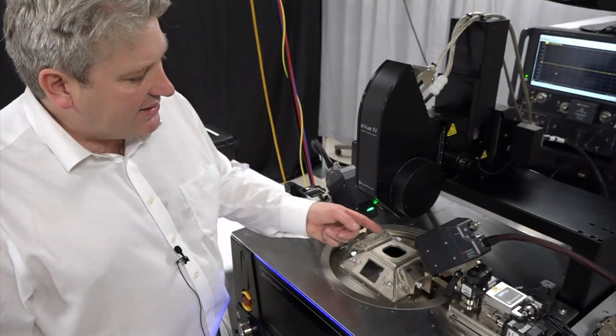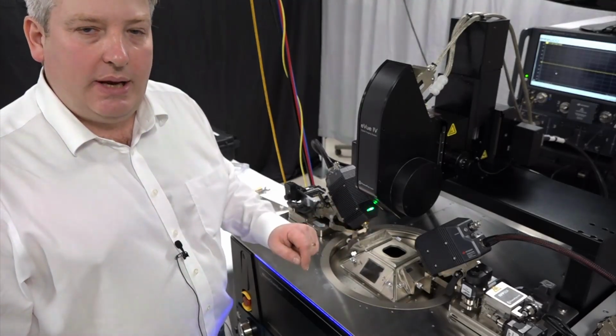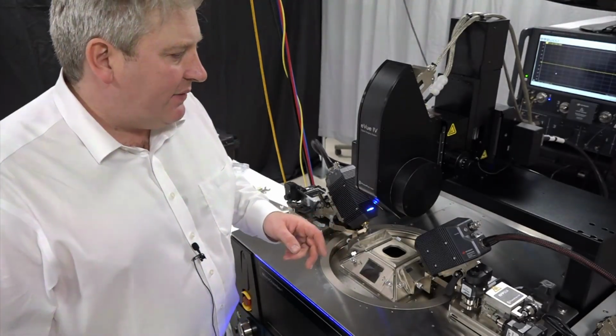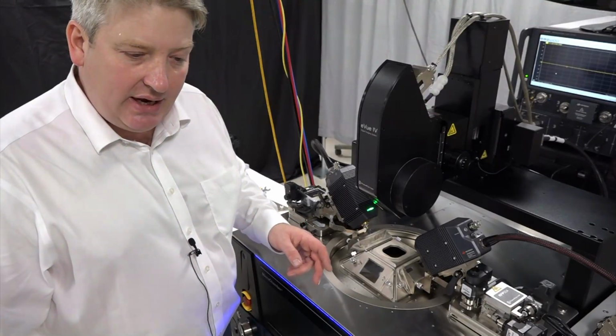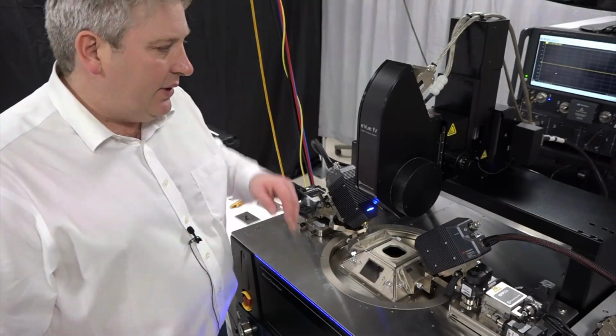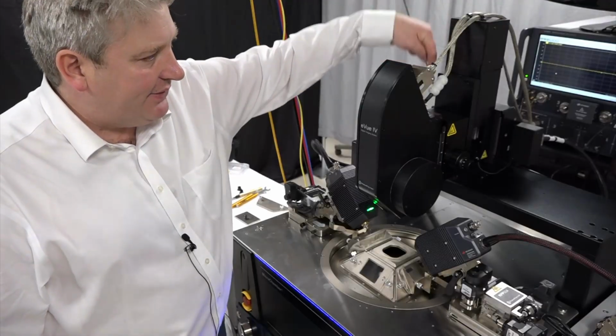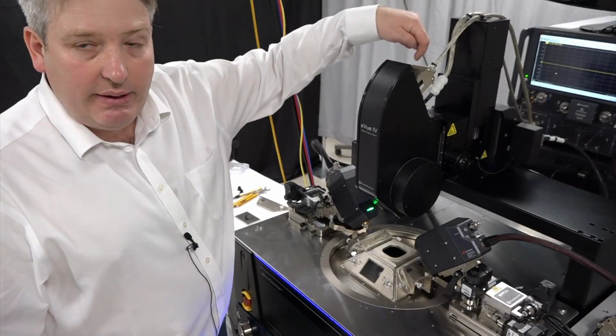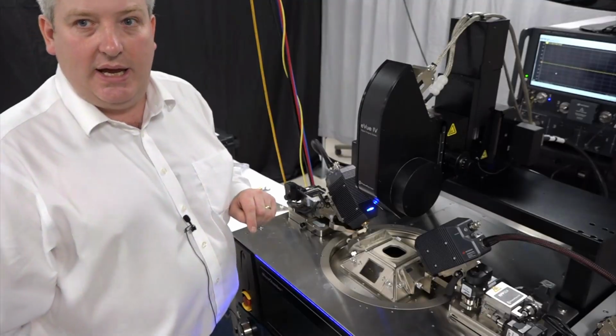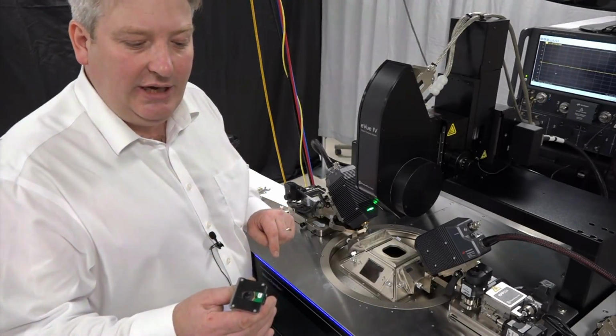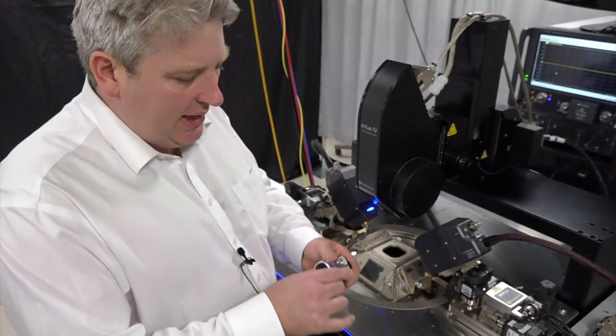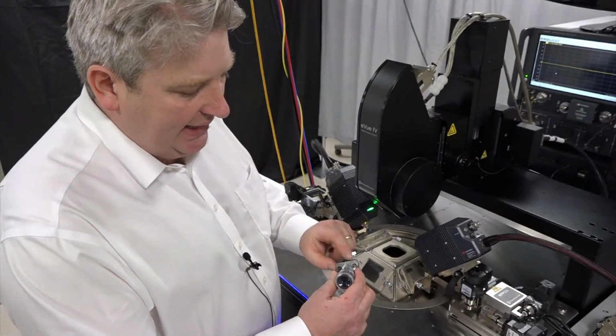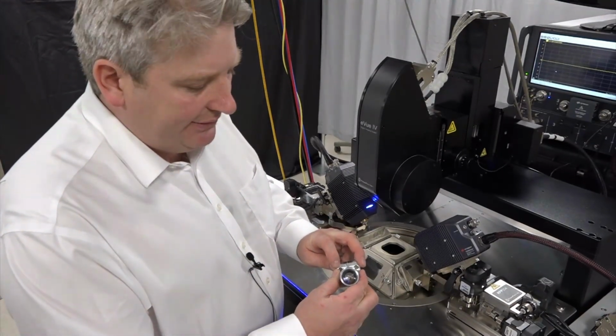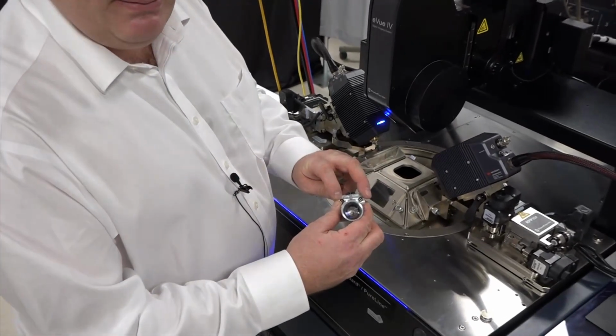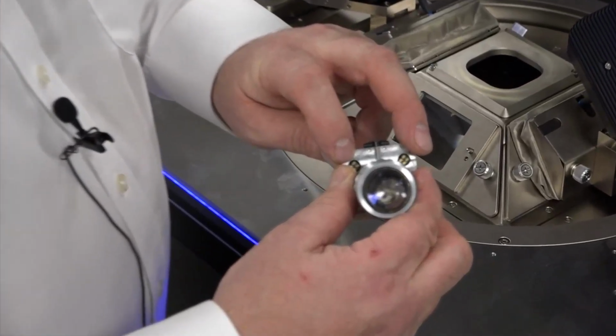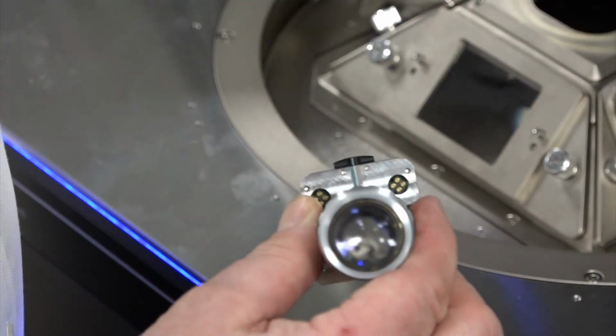The other thing which is good about it is the eVue IV has crash protection, so it will retract the objective. And in the case of an elite prober or a CM300, the scope transport, the actual lift, is a motor, so it will stop that motor on the way down if it detects a crash for the eVue. It's very convenient. That crash protection is done in conjunction with these terminals that you see here. If these terminals lift off their seat, then the system will detect that and use that as a means of detecting the crash, by which it will retract the mechanism inwards.